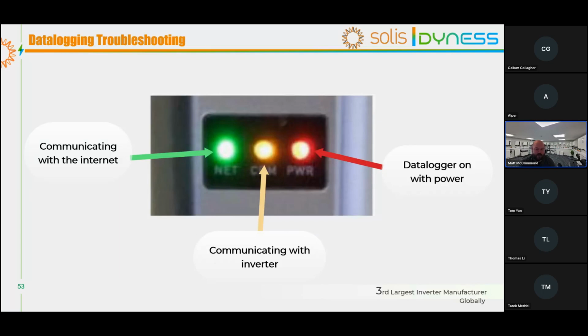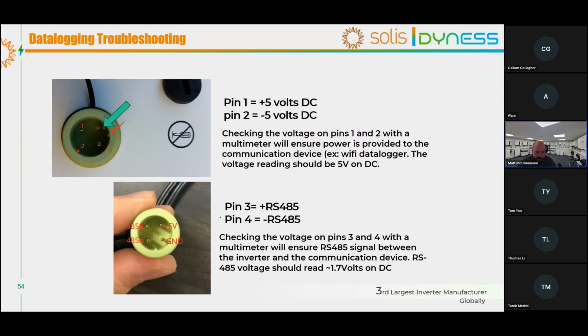The power comes from the inverter, and the RS-485 communication comes from the inverter. So what we can do at the bottom of our inverter is check if you're actually getting these values coming out of the inverter. For example, if no lights were coming on in the data logger, and we checked the pins here, and there was no voltage between pins 1 and 2, then we know that there's a problem with that port. Then you would call our service line, explain to them what we've done, and then we would take action from that point. Sometimes the cable internally can disconnect from the board, and it's just a small sort of bus connector. They might ask you to put that back in, but that's something that service would always ask you. It would not be something that we would ever expect you to do on your own. So you would contact our service department. They can talk you through that.